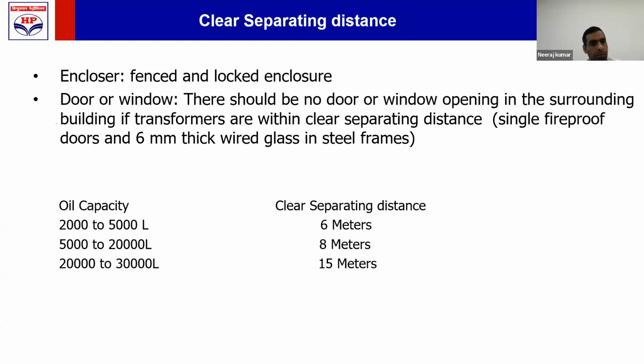So if we are using the first technique, that is, you are maintaining the separating distance. You are providing your transformer in such a way that no other installation or equipment is kept close to it. If there is fire in the transformer, no other equipment will be affected. Then how should that be done? That should be done based on the oil capacity. If your oil capacity is 2,000 to 5,000 liter, you have to maintain 6 meter clear separating distance.